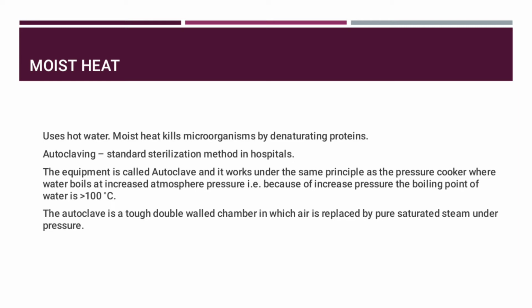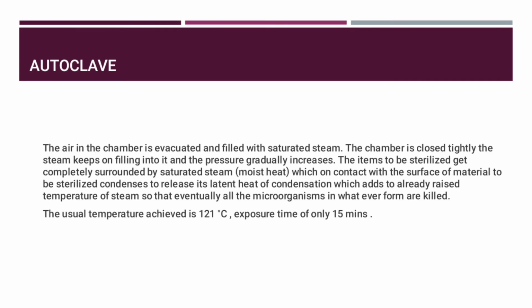The autoclave is a tough double-walled chamber in which the air is replaced by pure saturated steam under pressure. The air in the chamber is evacuated and filled with this saturated steam. The chamber is closed tightly, the steam keeps on filling into it and the pressure gradually increases.